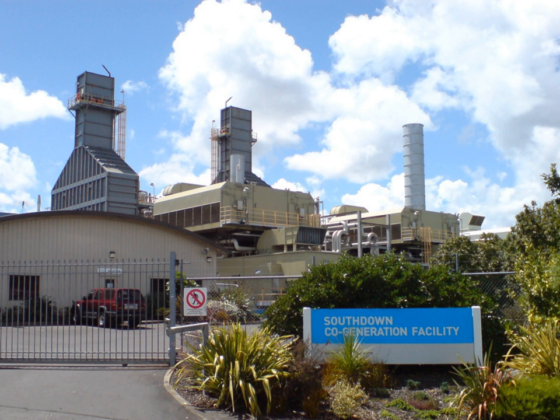Cogeneration systems, built in recent years in cold climate countries, utilize the waste heat produced by large power plants for heating by piping hot water from the plant into buildings in the surrounding community. However, it is not practical to transport heat long distances due to heat loss from the pipes. Since electricity can be transported practically, it is more efficient to generate the electricity near where the waste heat can be used. So in a µ-CHP system, small power plants are instead located where the secondary heat can be used, in individual buildings.